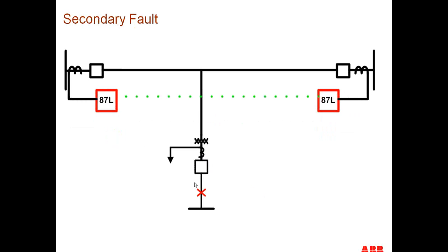Here's an example of a secondary fault that we would have on the tap, where even if we set this above load current, we could still possibly get a misoperation because of this secondary fault. But we know a couple of things about a fault on the secondary of this transformer. Number one, we know that there's a transformer impedance associated with this fault. So the fault current at the tap is going to be much less than the fault current flowing on the line and down to the tap. So we could use that information in our relays.